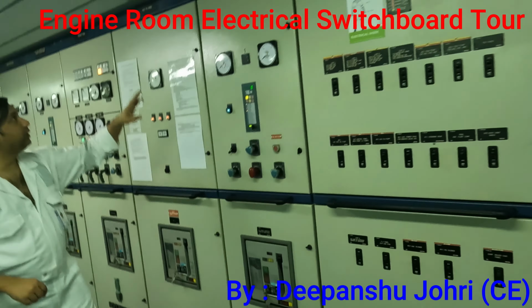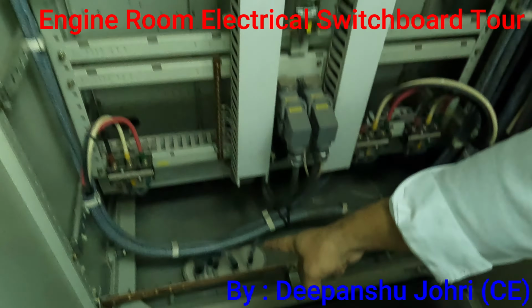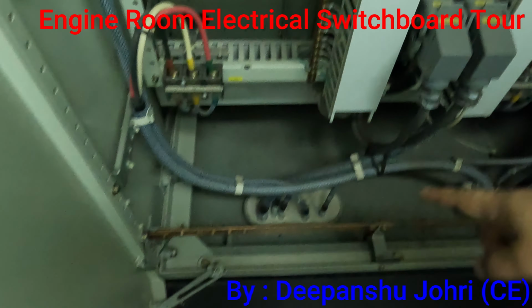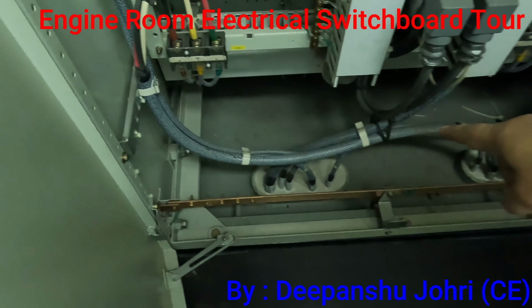You can see these wires entering from the bottom. In a switchboard, the wire should always enter from the bottom, never from the top, which is what I had been doing in my house. And you see this copper strip going for the earthing, with these wires connected here.